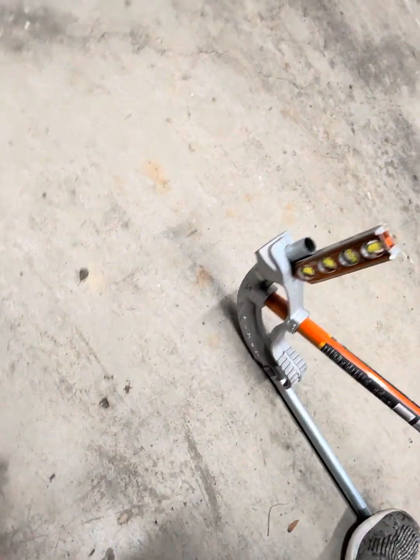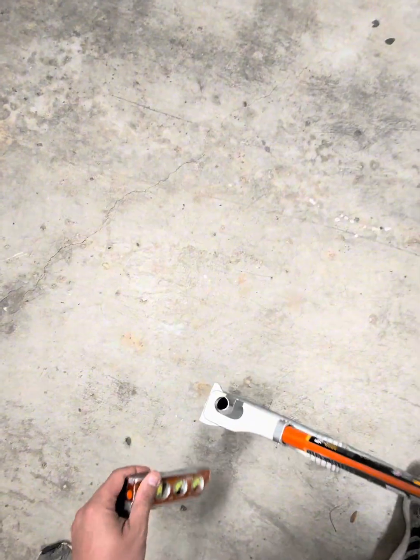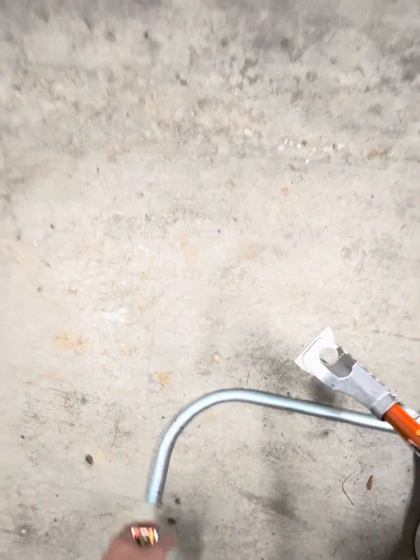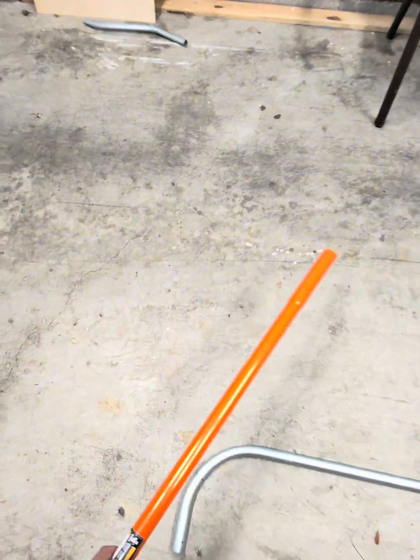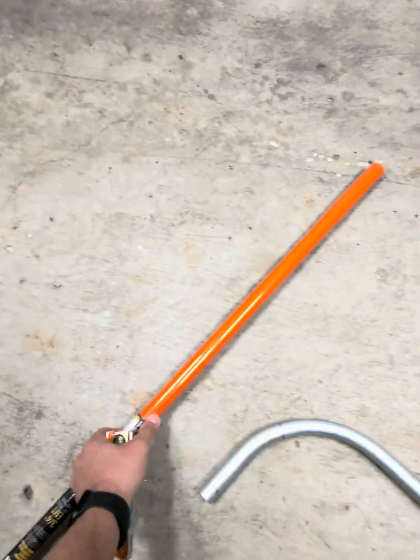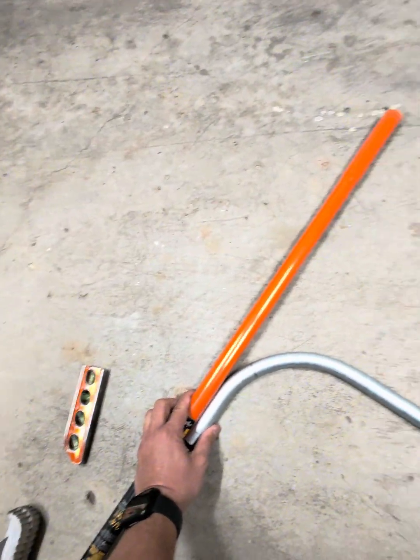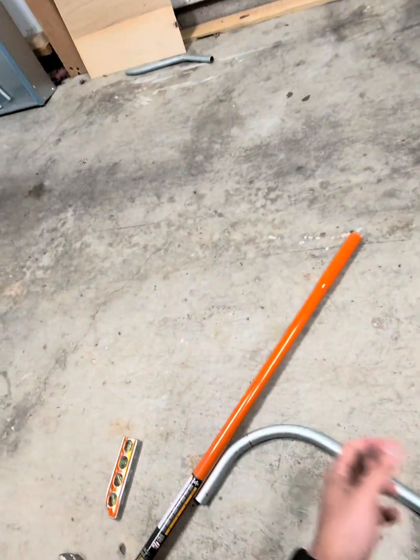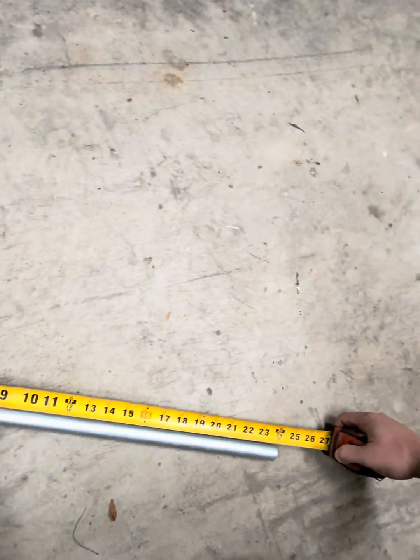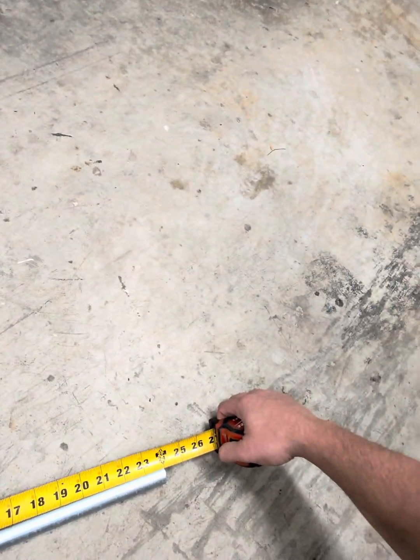Make sure it's level. And from there, what I like to do, I'll take a straight edge, whether it's a piece of wood, a piece of conduit, in this case my bender. Set 24 inch 90. We're within a sixteenth of an inch as you can see. Not exactly the brightest crayon in the box, but we're at 23 and 15 sixteenths to be exact.